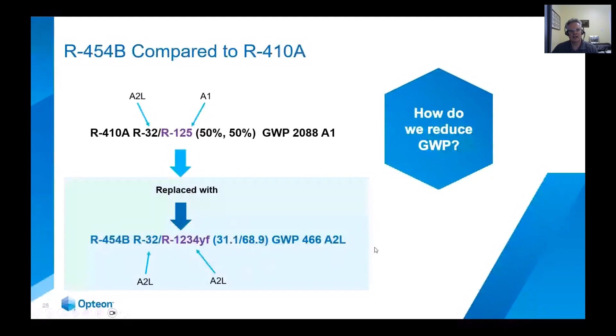But it also shows you that for 454, there's A, B, and C. They're all made up of these two refrigerants, 32 and 1234YF. The difference between A, B, and C is different percentages. So this is what ASHRAE Standard 34 looks like. Anyway, I just thought I'd give you some insight as to how that came about. Now, 410A versus 454B, how do they look? I don't want to spend a whole bunch of time, but pressure-temperature wise, very close. This is a pressure-temperature chart, very similar in performance in terms of vapor pressures, energy efficiencies, capacities. And that was really one of the cool things about 454B. It really looks like 410A.